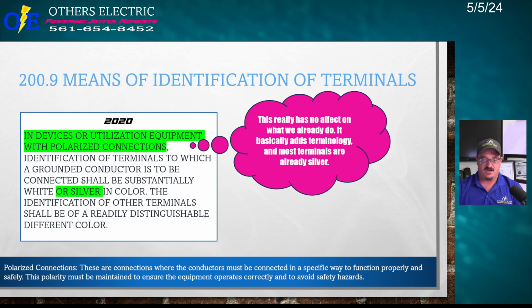So what they're talking about is a grounded conductor is your neutral. In equipment with polarized connections, it's just saying that it can be white or silver. They added the or silver. No major change, because most everything we get is already white or silver. So this really has no effect on what we do. We already do. It basically adds terminology, and most terminals are already silver.